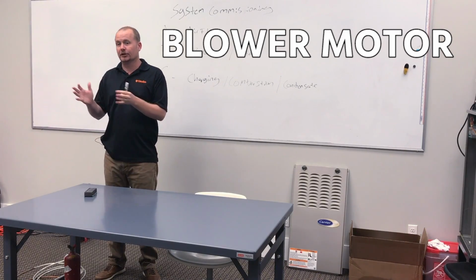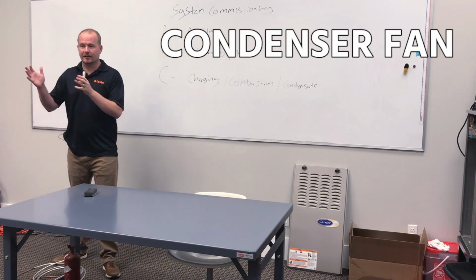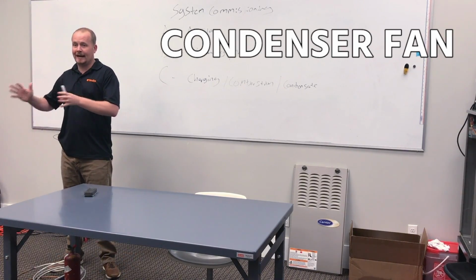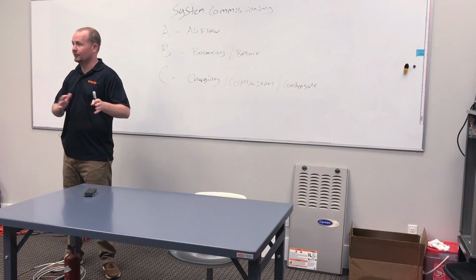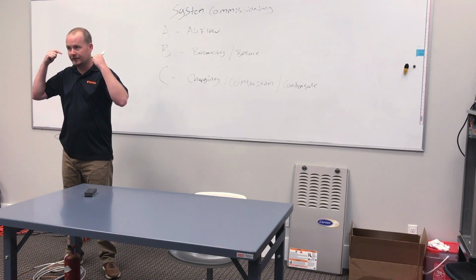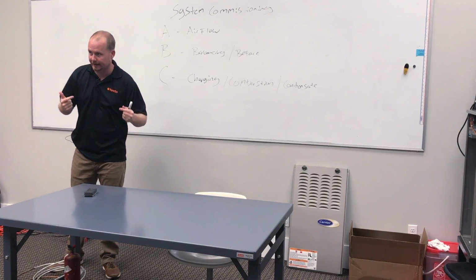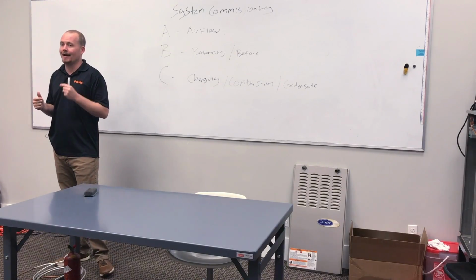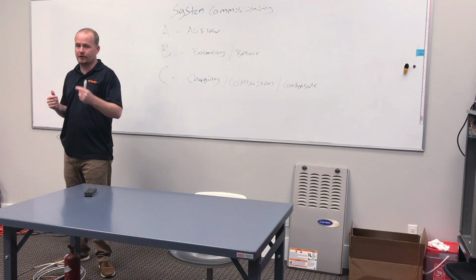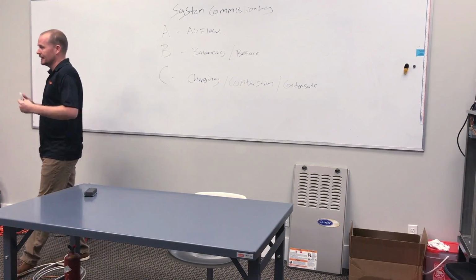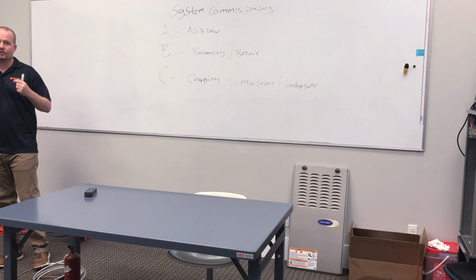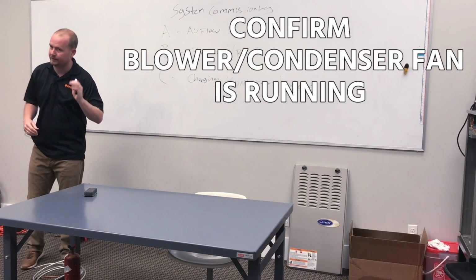You just can't. But there's another airflow, the condenser fan, right? So your condenser fan is your other airflow. You have to have both of those airflows. They both have to exist first. So you make sure they exist by just listening, right? And that's actually a step I never want you to skip. Whether you're doing a service call or a system setup, I never want you to skip the step of just confirming that, hey, blower's running, condenser's running.